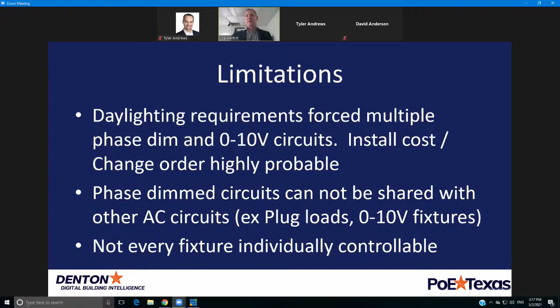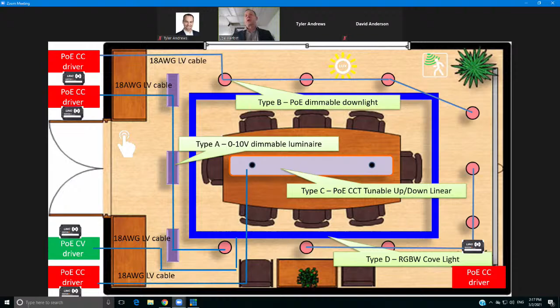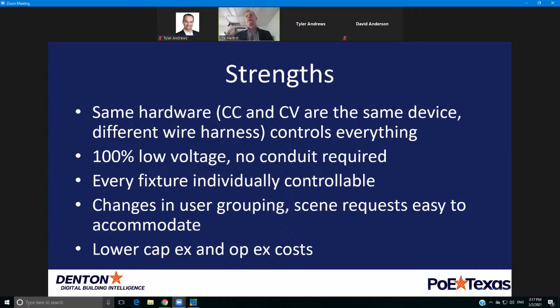I bring in PoE, and now I use the same hardware but program each fixture individually, since it's individually controllable, to respond differently to things like the daylight sensor or occupancy sensor. With PoE technology, I can move a lot of that differentiation into software and have the same physical hardware control all of this. Strengths are that it's all low voltage, no conduit requirements, changes are very flexible — I can change who responds to what whenever I want — and I've got lower CapEx and operating costs.